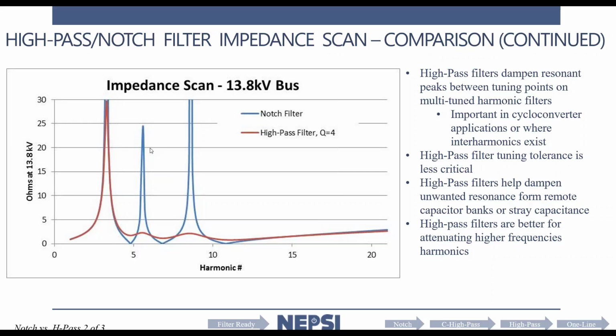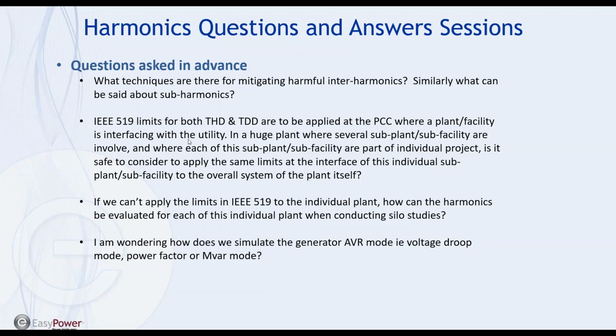And in so doing, we get this red curve. A C high pass filter has more losses, but it does not have the resonant peaks that a standard notch filter system has. So what I'm trying to say here is that to eliminate the concerns related to interharmonics, or the non-integer harmonics, you would typically use a C high pass or high pass filter.